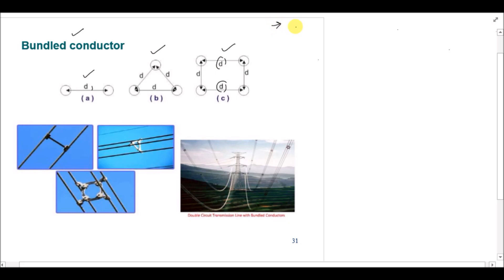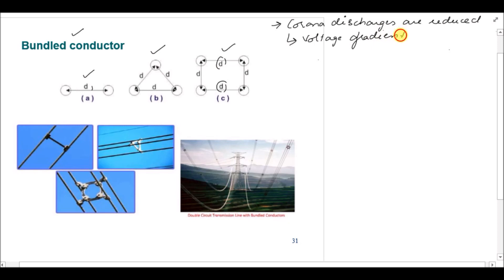The first advantage of using bundle conductors is that corona discharges are reduced. As we know, corona discharges occur when we have a large voltage gradient over the surface of the conductor. So if the voltage gradient is reduced, the corona discharges will reduce. The voltage gradient is the difference in potential gradient over a conductor surface. If corona is reduced, the power losses over the surface of the transmission line are also reduced.